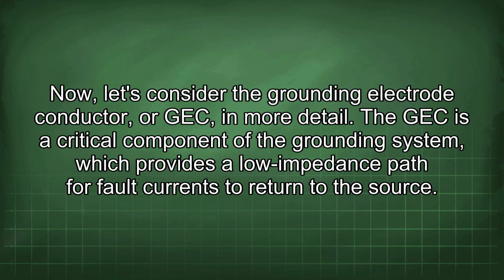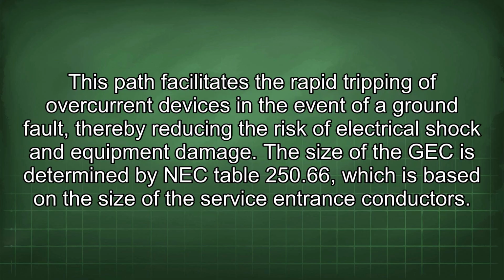Now let's consider the grounding electrode conductor, or GEC, in more detail. The GEC is a critical component of the grounding system, which provides a low impedance path for fault currents to return to the source. This path facilitates the rapid tripping of overcurrent devices in the event of a ground fault, thereby reducing the risk of electrical shock and equipment damage. The size of the GEC is determined by NEC Table 250.66, which is based on the size of the service entrance conductors.